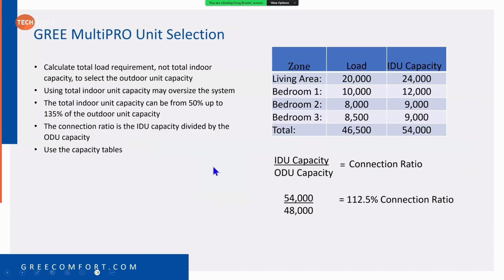So how we calculate that connection ratio. It's easy math. It's the same thing that selection software is doing. It's the same thing that the system builder app is doing. You have to have no more than 135% connected capacity. So it's got to be between 50 and 135%. So this is just kind of giving you an example.